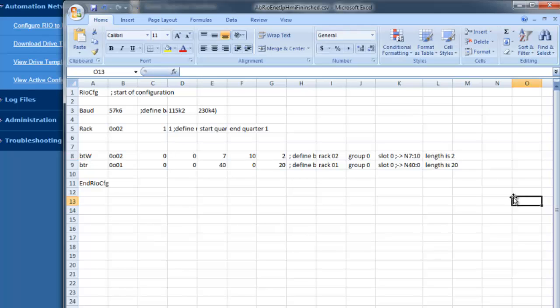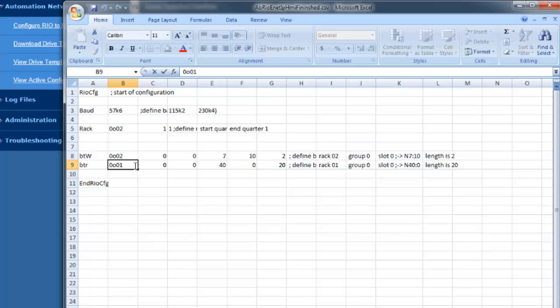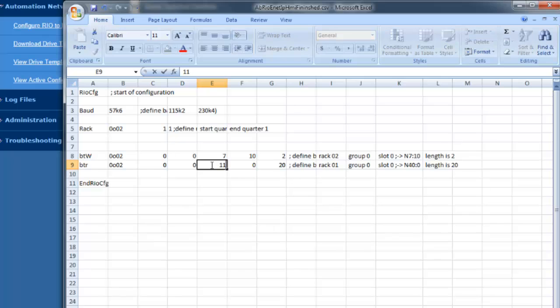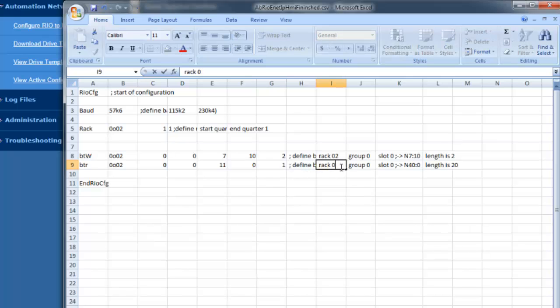We'll edit the definition on what we just programmed for our own documentation. Next, we'll configure the block transfer read for rack 2 group 0 and slot 0. The file that the block transfer read was using was B11, so we'll put in B11 starting at word 0 for a length of one word. And again, we're just going to edit the definition.